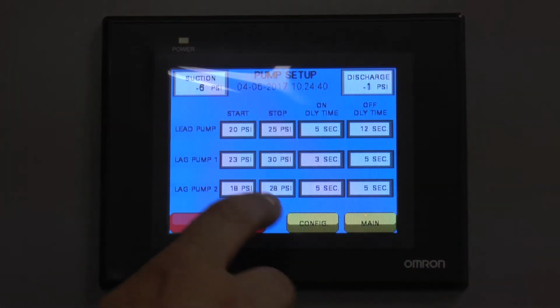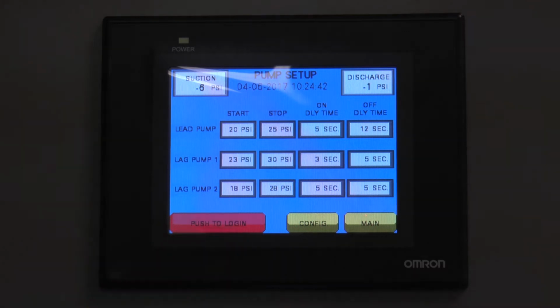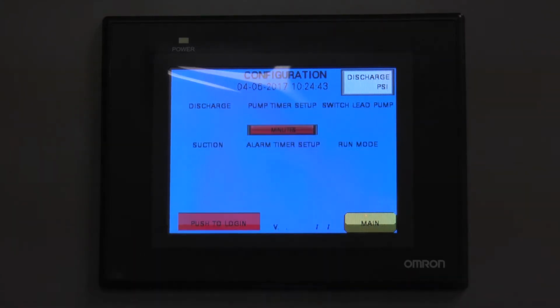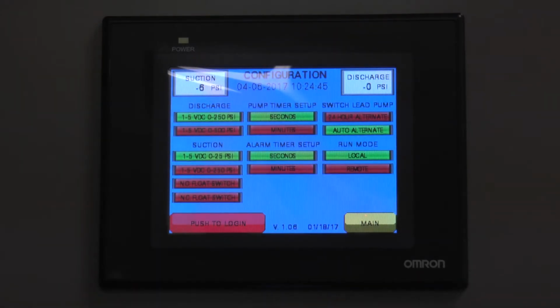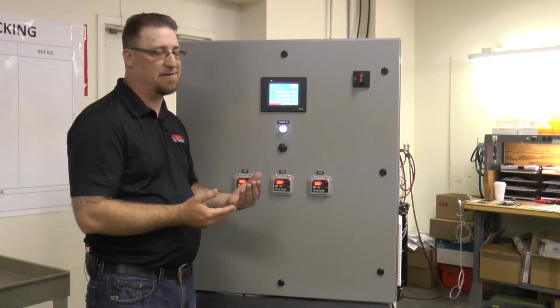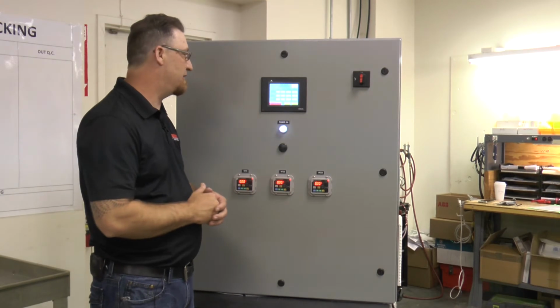So if we press the pump setup button, right now this is a triplex system. So we have lead pump start, lead pump stop, on delay, and off delay times. Now we can configure those to minutes, seconds, and we can also alternate these pumps every 24 hours or every time that the system calls for water.